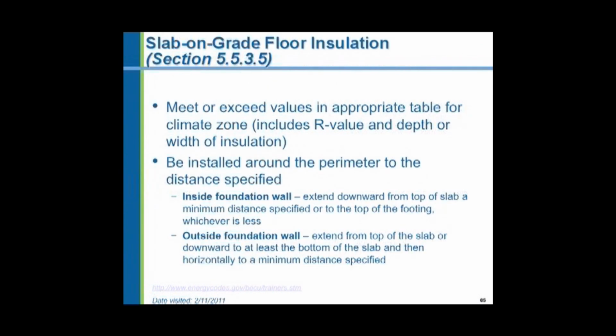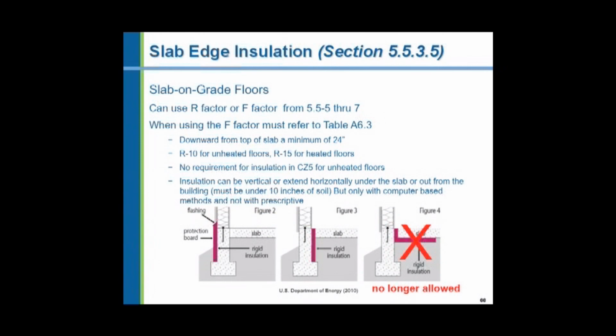Slab on grade floor insulation. This is very common in commercial buildings. Many small strip malls and individual office buildings are designed with slab on grade. And there are specific requirements for installing the insulation on slab on grade buildings. You can put it on the exterior. You have to protect it from damage and sunlight on the exterior. You can put it on the interior. However, this is an interesting little application that is permitted in residential construction, but not in commercial.